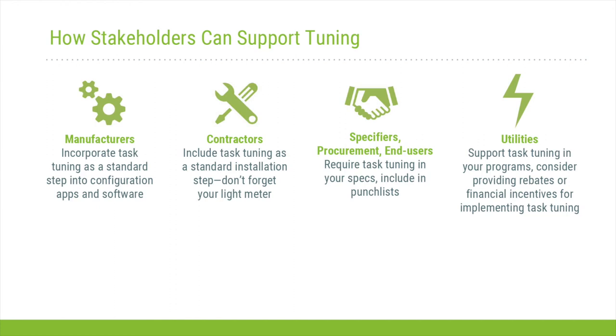Just going off the perception of, yes, this feels bright, if you're not doing it at the right time of day, which I would encourage you not to do when there's no daylight out, or you don't have the right amount of occupants in the space. If you have one contractor go room to room just eyeballing it, you're probably not going to get the results you want. So you either want to commission with an illuminance meter or with the people in the office, but that may not be easy because of getting them in during evening hours and some of the other logistical things.